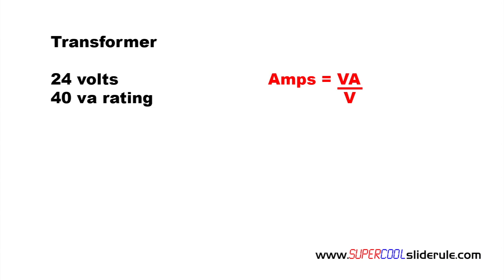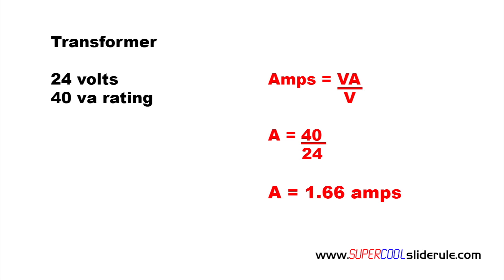A VA rating of 40 is converted to amps by dividing the VA rating by the voltage output, as seen here. In this example we will divide 40 by 24. This gives us 1.66 amps. So this transformer will deliver a maximum of 1.66 amps at the rated output of 24 volts.